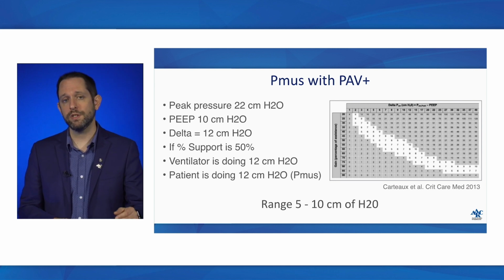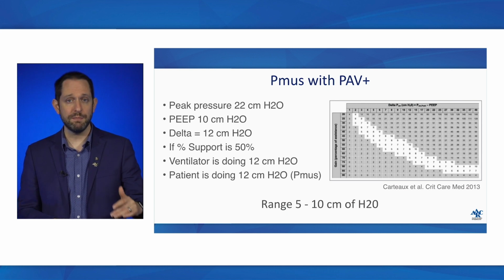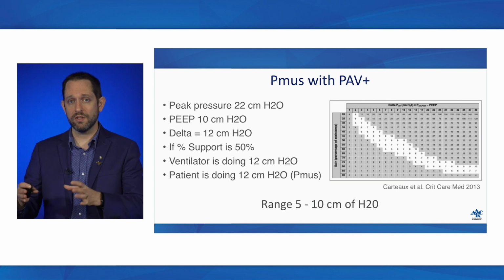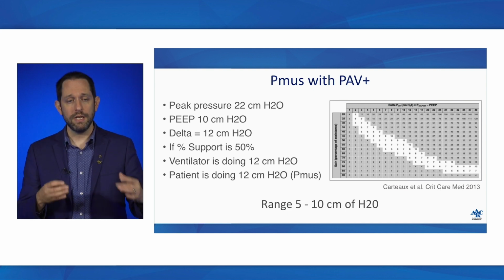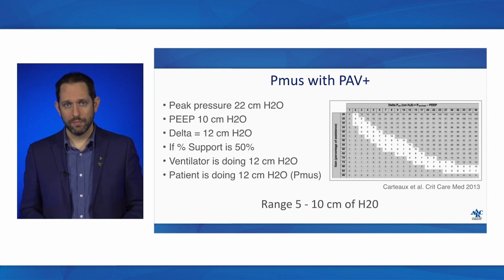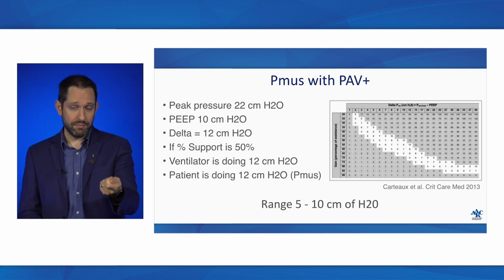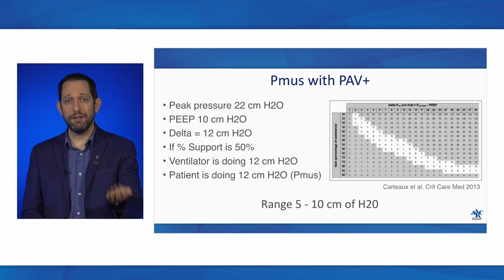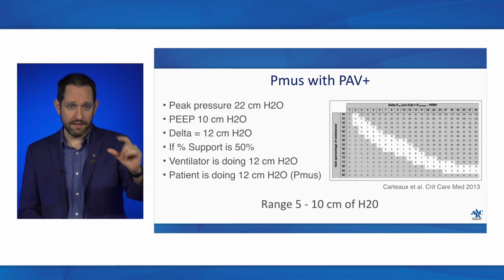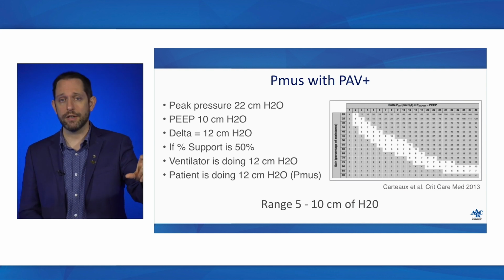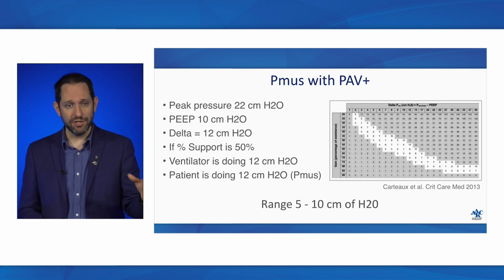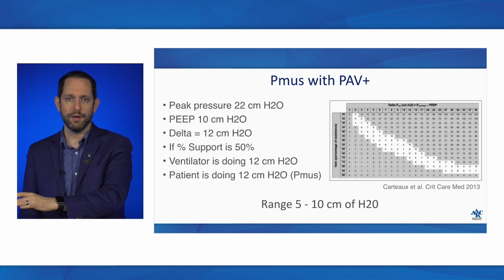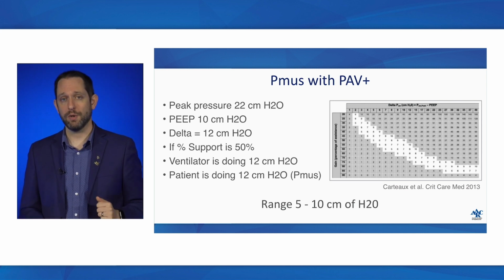If my peak pressure is 22 centimeters of water and my PEEP is 10, the delta pressure being provided to the patient by the proportional assist mode or the PAV+ mode is 12 centimeters of water. If my PAV+ percent support is set at 50%, I know that that delta pressure being delivered by the ventilator is 50% of the total work. Therefore, the patient is doing 12 centimeters of water of muscular pressure or work by them. So now I know that they're doing 12.